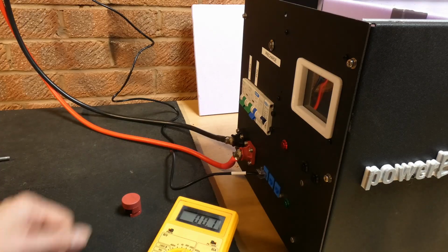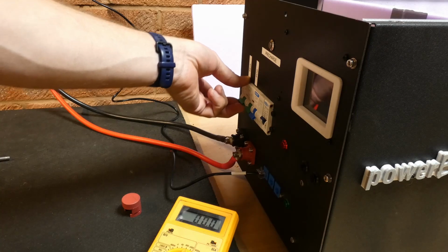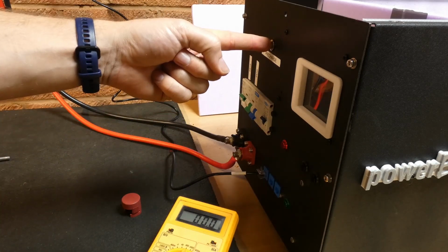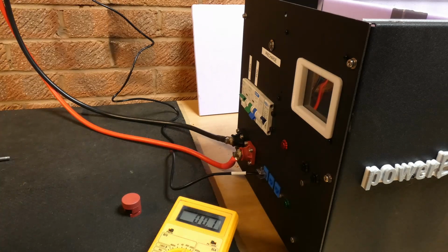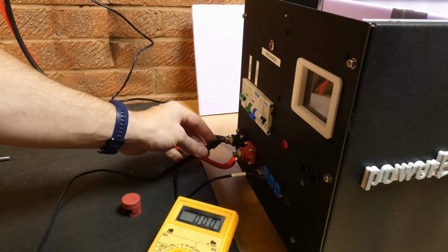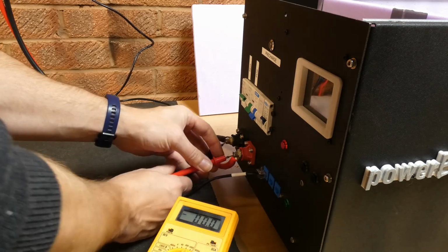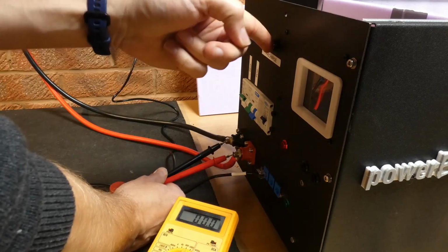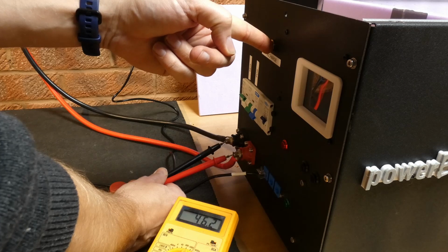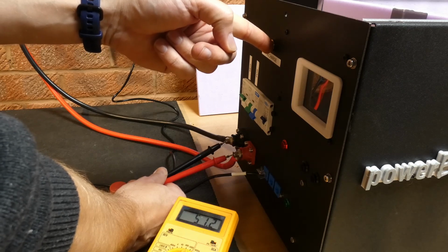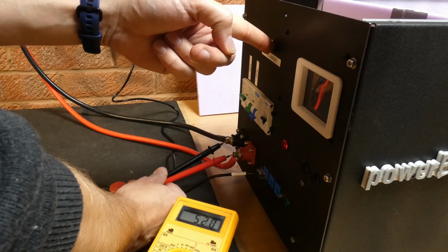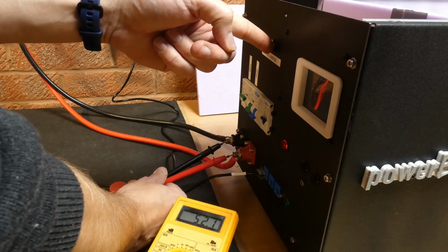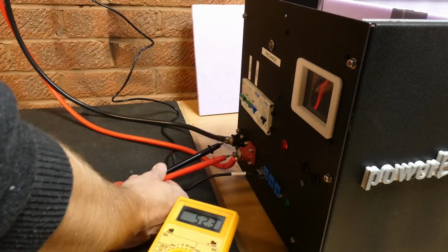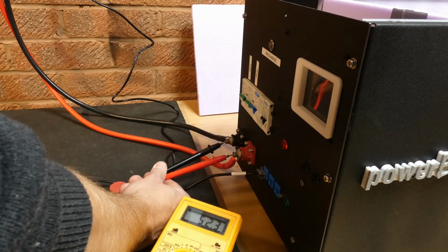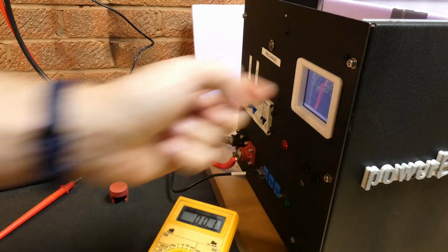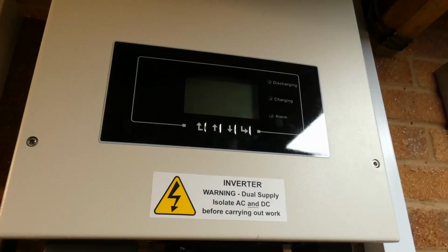Right, the moment of truth. So we should switch on the negative, hit the pre-charge button. In fact, if I put my voltmeter on this, I might be able to stay there. Hit the pre-charge, it charges up the capacitors, so you can see the voltage slowly rising until it gets to the full 52 volts, and then I should be able to turn this on, and that's great. No smoke, no steam. All good, the DC is now on.